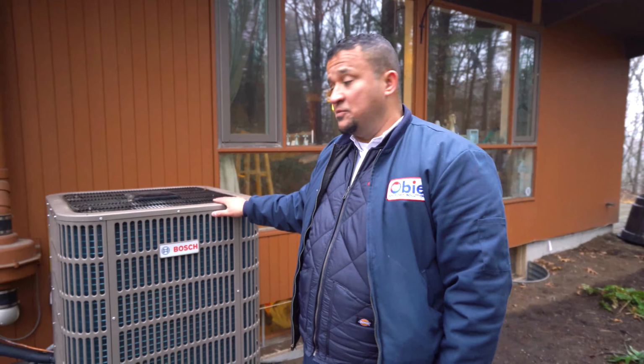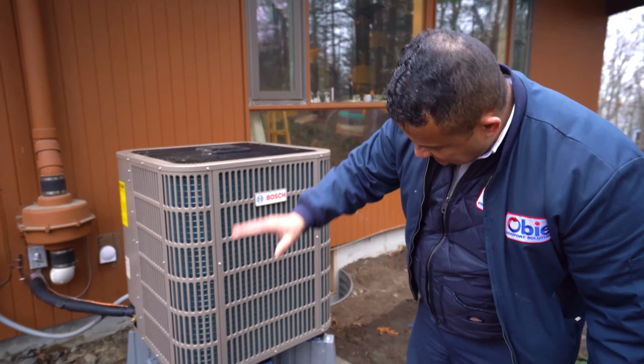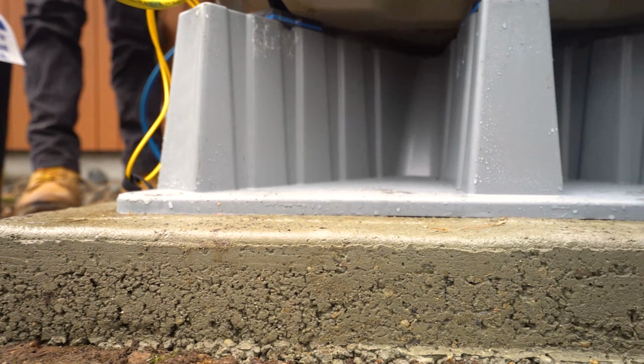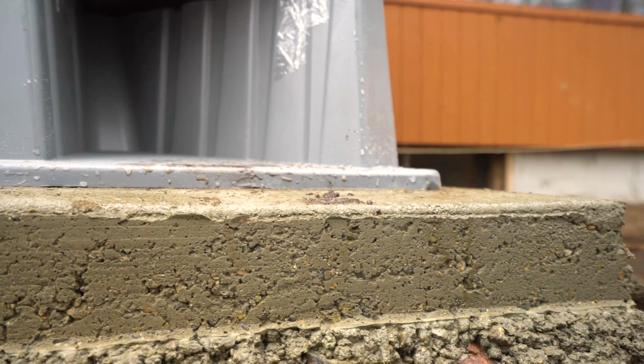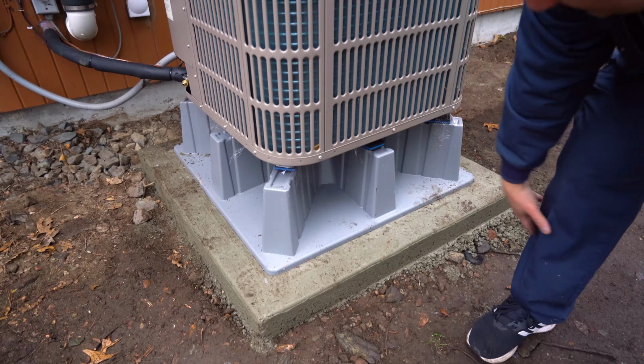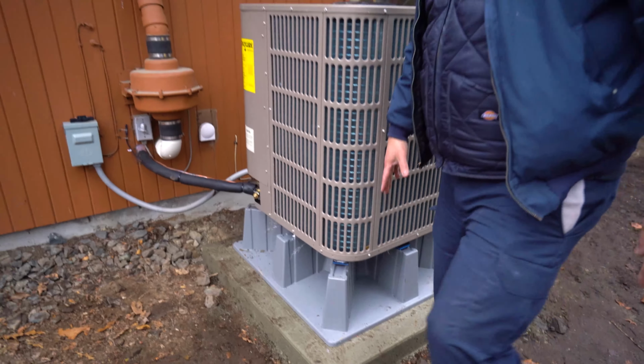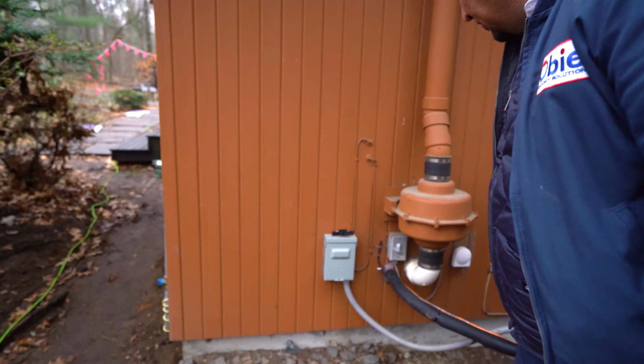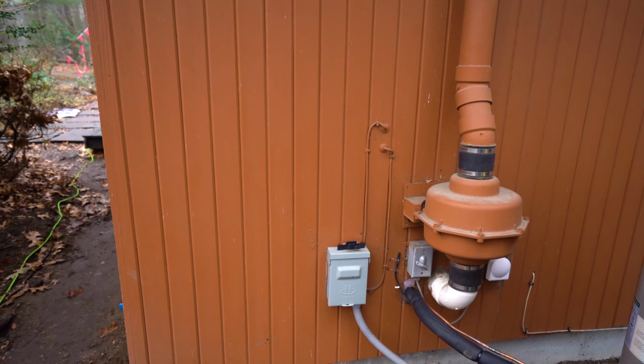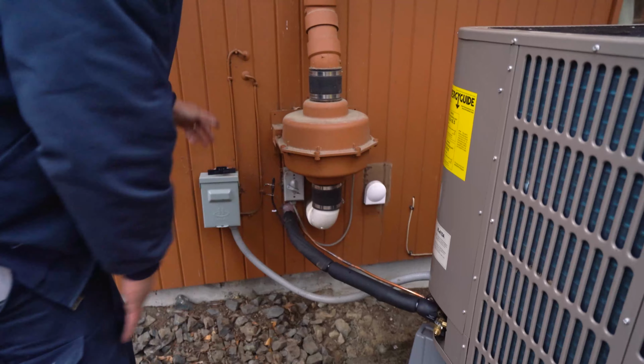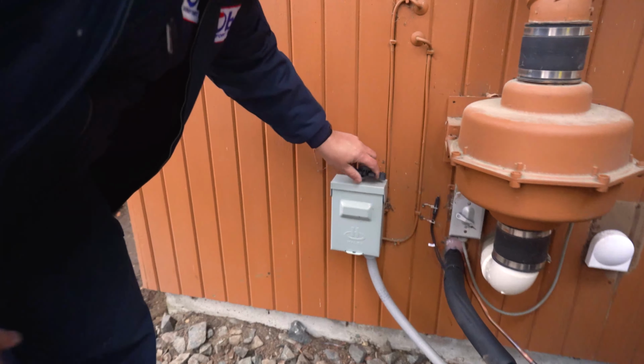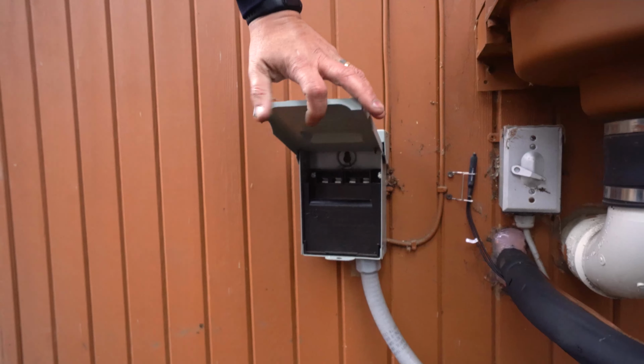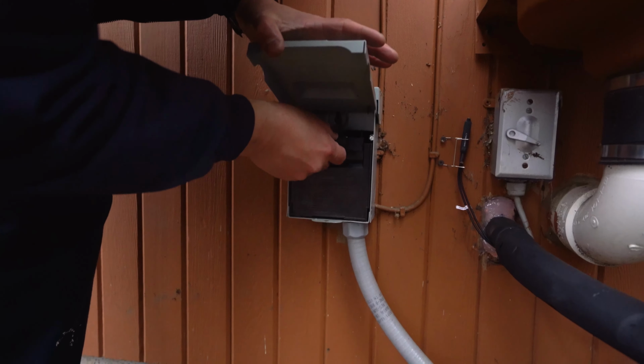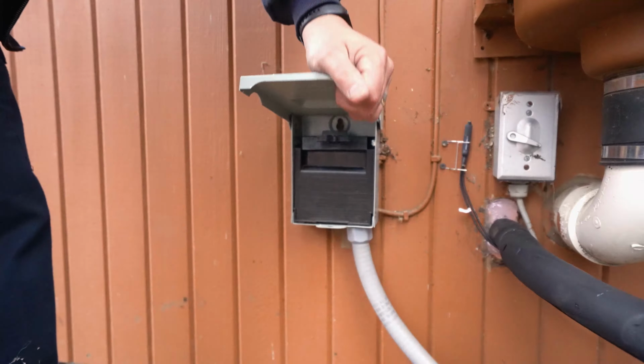So now the system is complete, system installed. You see the base, instead of wood, you have the proper riser pad that makes sure you have enough space for the defrosting, with the concrete pad. You have the lines redone. You see now you have full access to the electronics and everything inside of the unit. You don't have to be squeezing back there. In here you have the disconnect. Actually, this was not part of it, we already fixed this inside, so to turn it on and off you just have to pull this back in here. System is ready to go.